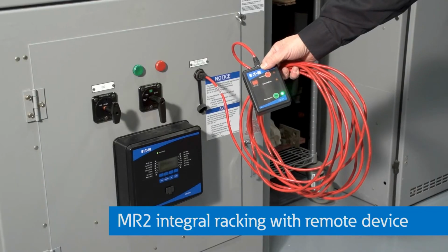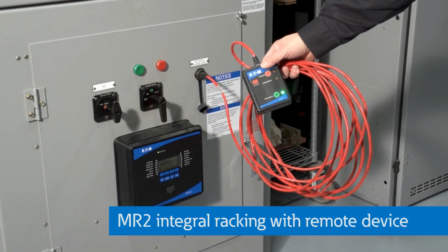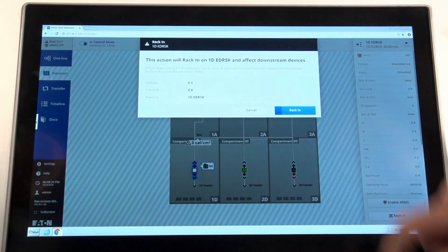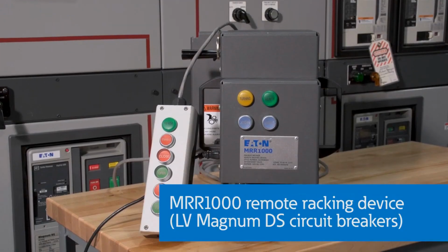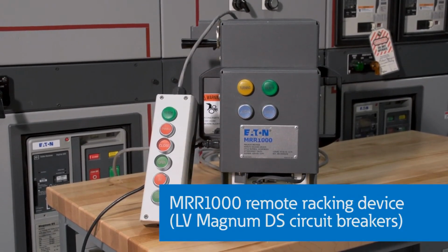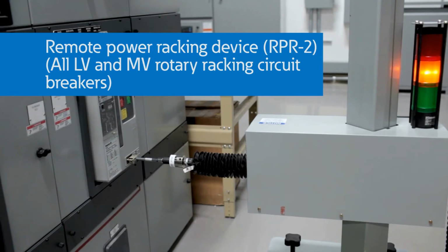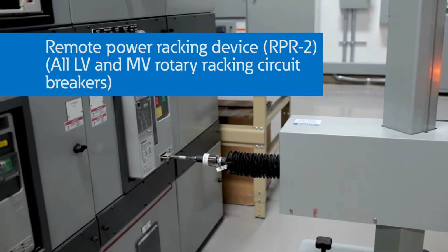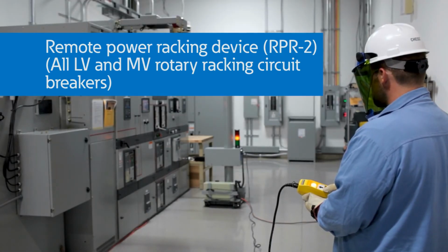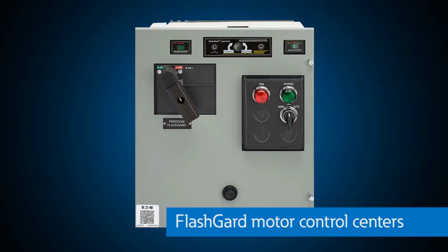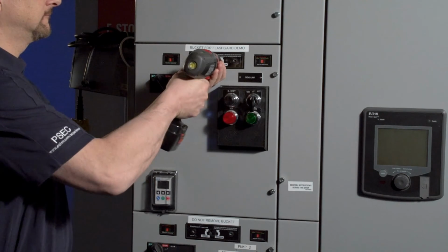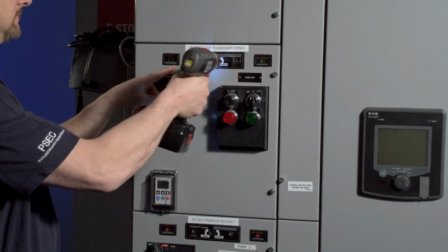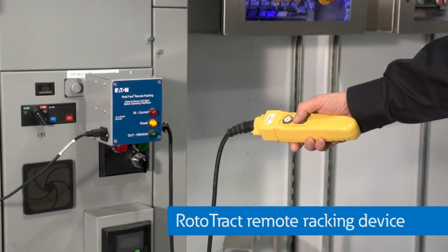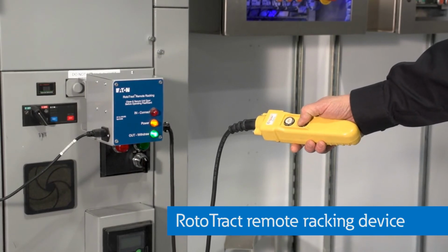This includes integrated racking that can be remotely operated with a pendant like this one or through an HMI. It also includes these MRR1000 and RPR2 racking devices that can be installed and then controlled from a safe distance away, as shown here. Finally, for motor control centers, this FlashGard MCC can be withdrawn from the live bus and installed with the door closed, even with this remote operator, to keep personnel out of harm's way in the event of an arc flash.